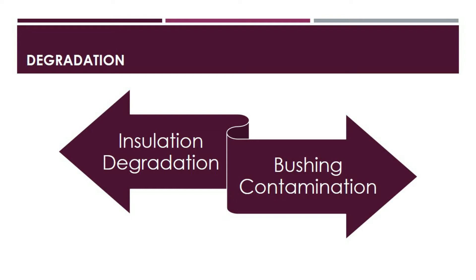The electrical loading profiles and the length of the transformer's service life have an impact on its asset life. Other factors, including mechanical damage, salt exposure, and voltage and current spikes, also have a significant impact. To assess the useful remaining life of distribution transformers, a mix of condition, age, and load-based criteria is frequently used.